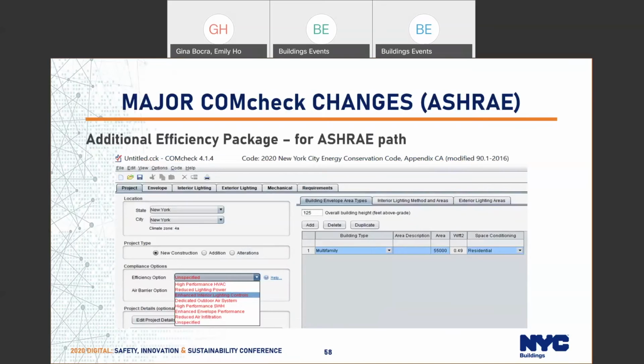So other major changes in ComCheck, we mentioned that there is now the high efficiency option for the ASHRAE path. So when you select the Appendix CA, modified 90.1 2016 version, you'll see the efficiency option that pops up. And here it's mandatory to select one, and then you have your option: high performance HVAC, reduced lighting power, enhanced lighting controls. You select one of these, and that'll be your designation for the project. If you select high performance HVAC or reduced lighting power, the minimum efficiency values within ComCheck will automatically update or populate. For everything else, you'll have to provide additional supporting documentation to show that you complied with those requirements. And that's the same under the ECC path as well.